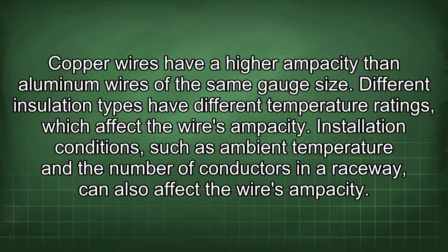Copper wires have a higher ampacity than aluminum wires of the same gauge size. Different insulation types have different temperature ratings, which affect the wire's ampacity. Installation conditions such as ambient temperature and the number of conductors in a raceway can also affect the wire's ampacity.